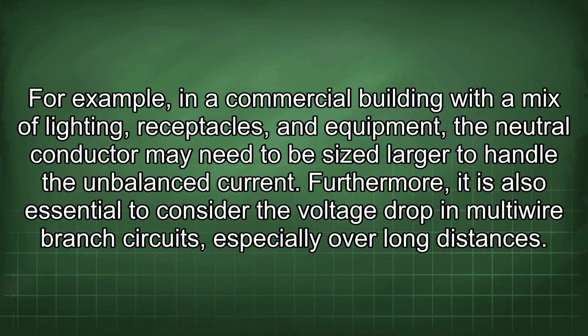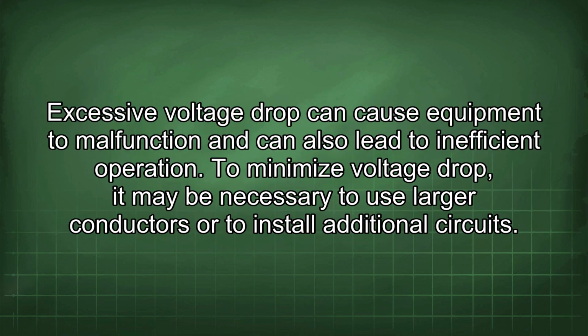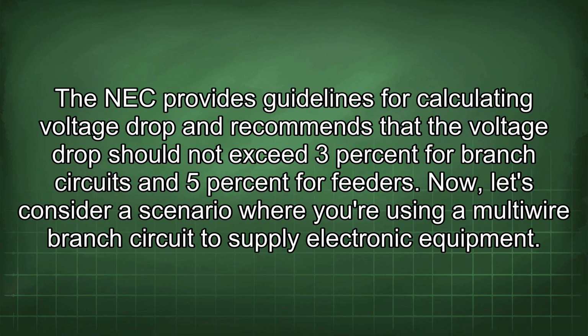Furthermore, it is also essential to consider the voltage drop in multi-wire branch circuits, especially over long distances. Excessive voltage drop can cause equipment to malfunction and can also lead to inefficient operation. To minimize voltage drop, it may be necessary to use larger conductors or to install additional circuits. The NEC provides guidelines for calculating voltage drop and recommends that the voltage drop should not exceed 3% for branch circuits and 5% for feeders.